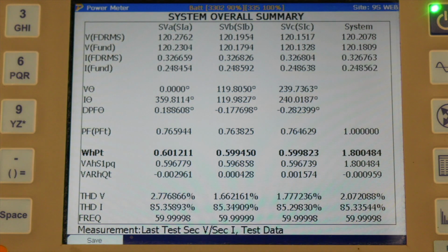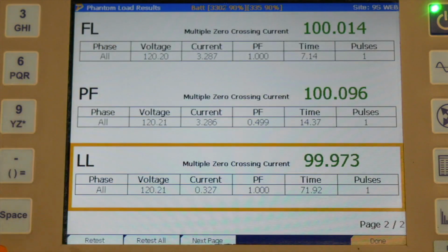Steve's correct. It was interesting. If I go back and look at these results, they look excellent. Meter registration looks perfect. But Steve is exactly right. What's going to break down is your transformers, especially. We've seen high harmonic distortions wear out transformers, tripling the neutral, wearing out the neutral phase. Eventually, if that neutral goes loose, it could cause a spark and a fire.